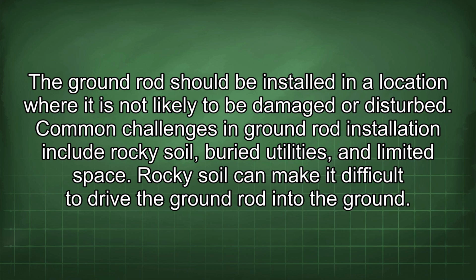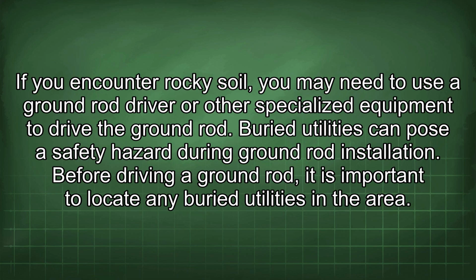Common challenges in ground rod installation include rocky soil, buried utilities, and limited space. Rocky soil can make it difficult to drive the ground rod into the ground. If you encounter rocky soil, you may need to use a ground rod driver or other specialized equipment to drive the ground rod. Buried utilities can pose a safety hazard during ground rod installation.